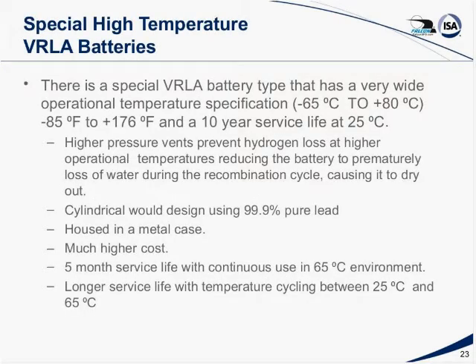There are special lead-acid batteries, VRLA batteries, out there that have an exceptional operational temperature range from minus 65C to plus 80C. They have a 10-year rated service life at 25C, and in the next slide we'll see that that life is not quite as high at 55 as the previous battery. They use, again, higher pressure vents to prevent the hydrogen loss. They're a different design.